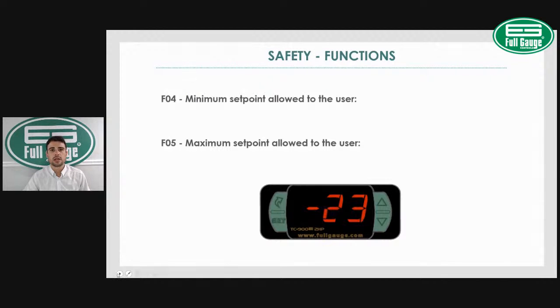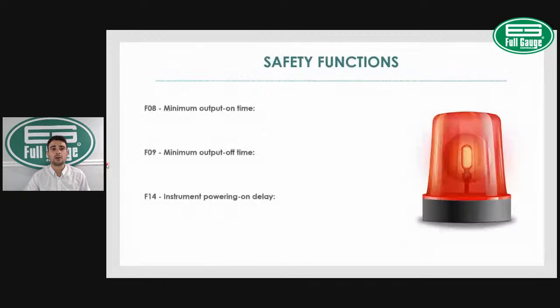Other safety functions loaded with the MT512 are minimum output on time and minimum output off time, F08 and F09. Why are those needed? Those functions serve to prevent short cycles on the compressor. For example, in some applications you're going to have a very narrow set point and differential. Let's say we have the set point at 32 degrees and my differential of 2 degrees. So the system will cut out at 32 and will cut in at 34. That's a very narrow set point and differential.